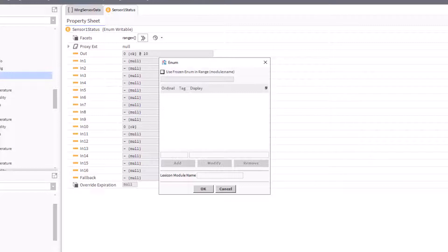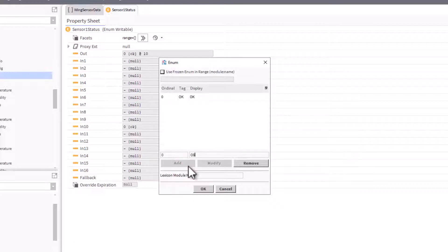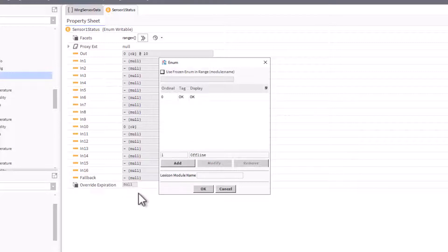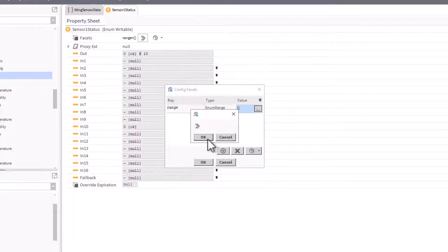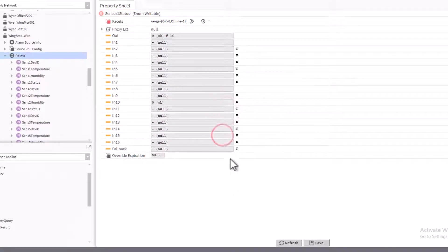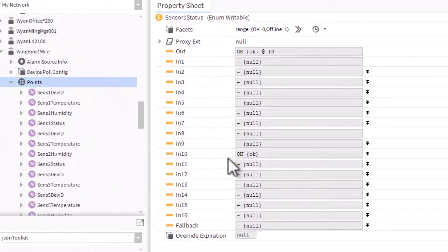Once the enum window opens, you don't see anything intuitive right away, but what you need to do is put your numeric value here and then your text value here. When working with sensor1 and reading in this data point, a zero represents everything is OK. Click add. The other data point available is when it returns a one, which means the sensor is offline. Click add, then click OK through the dialogs.